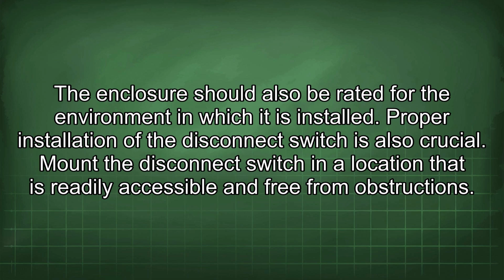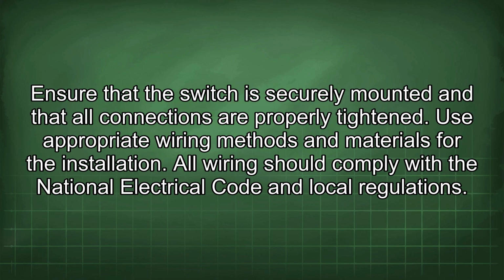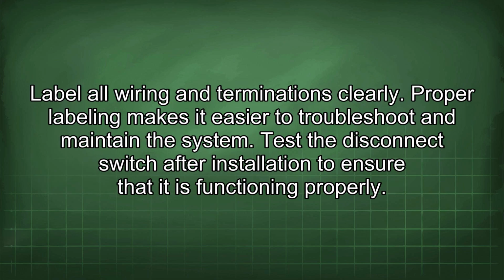Proper installation of the disconnect switch is also crucial. Mount the disconnect switch in a location that is readily accessible and free from obstructions. Ensure that the switch is securely mounted and that all connections are properly tightened. Use appropriate wiring methods and materials for the installation. All wiring should comply with the National Electrical Code and local regulations. Label all wiring and terminations clearly. Proper labeling makes it easier to troubleshoot and maintain the system.